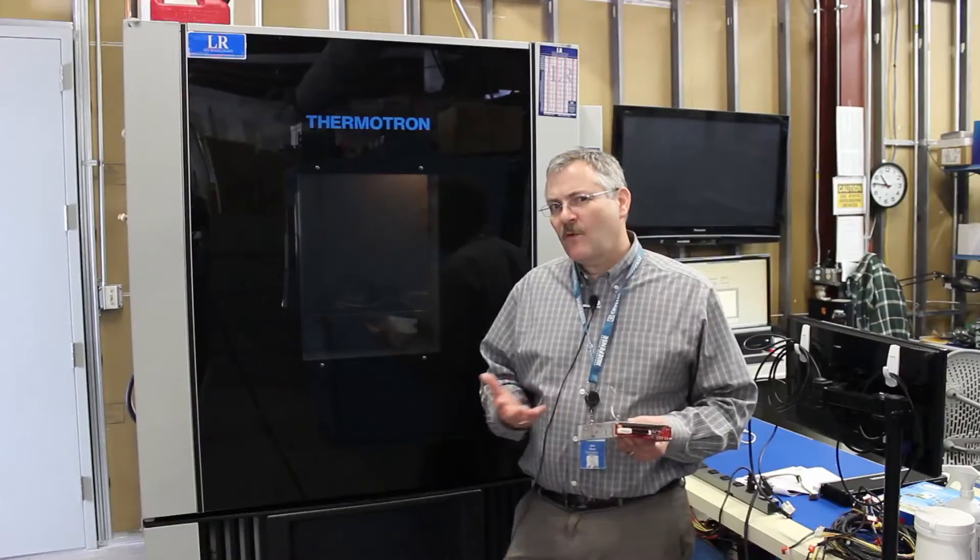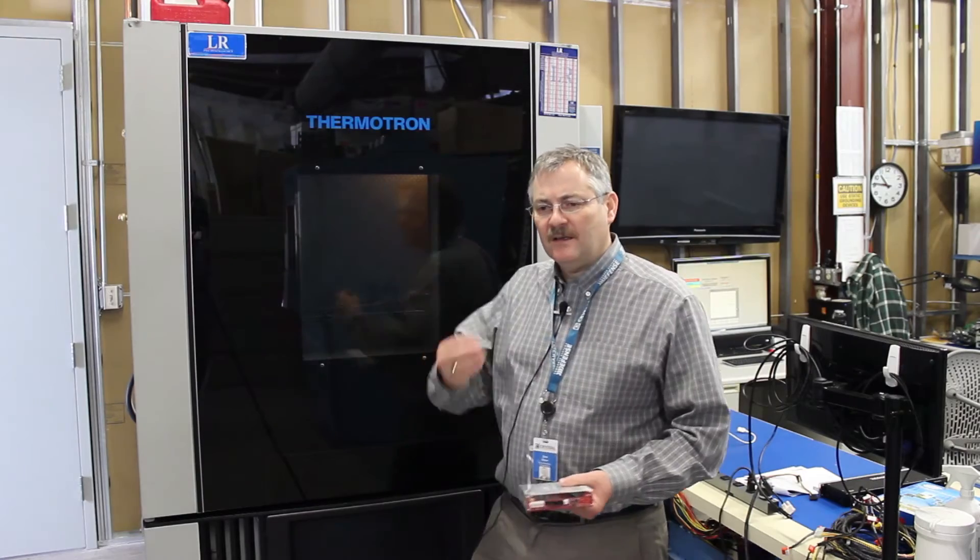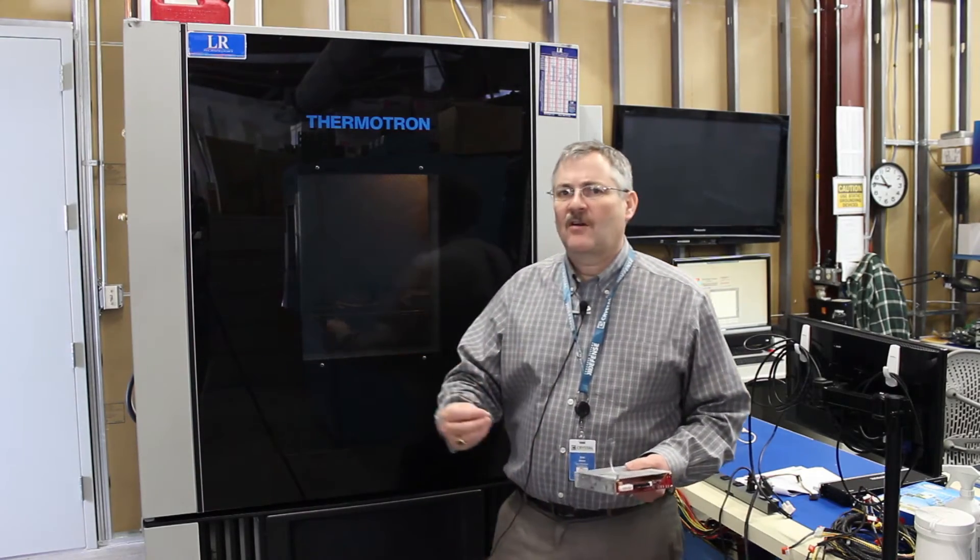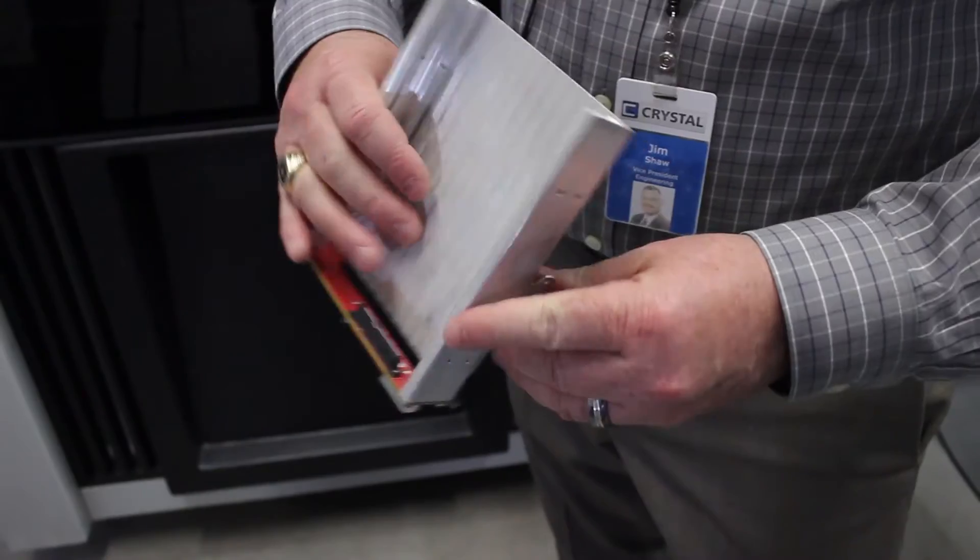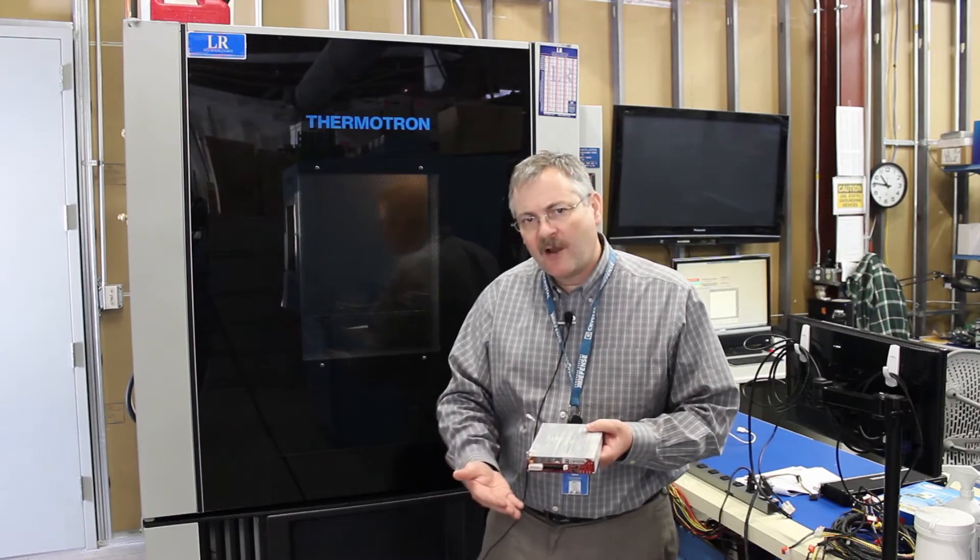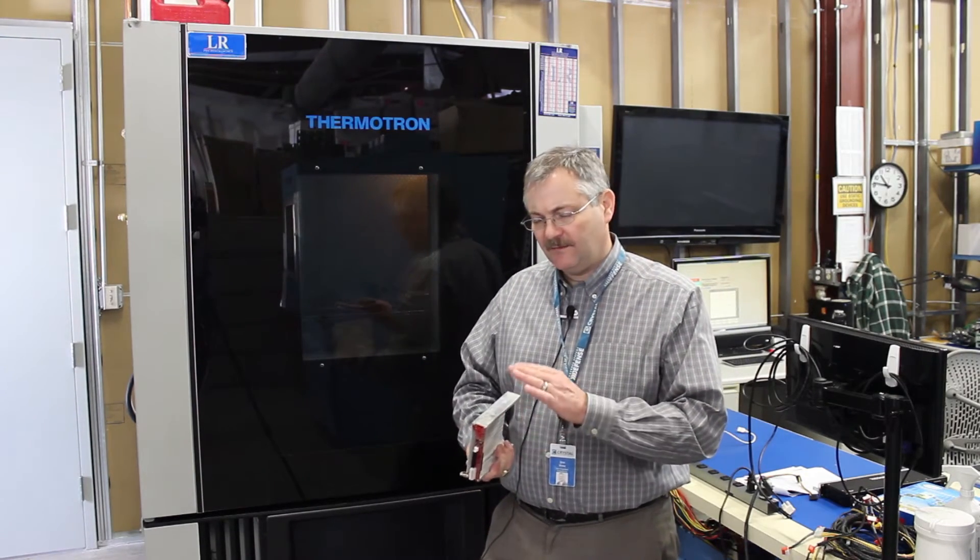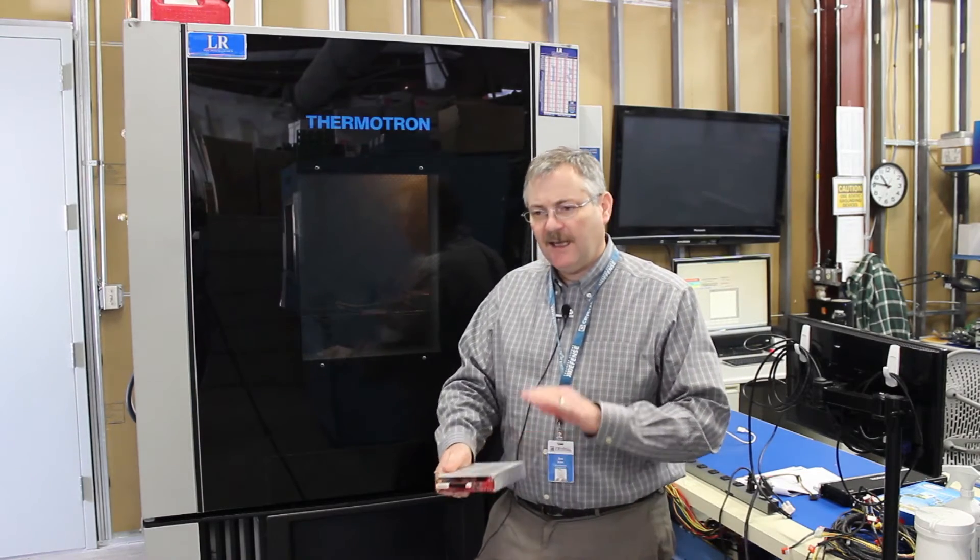So what are you looking for when you're doing these kinds of tests? This is a test about whether the moisture affects your circuit cards. Do the bonding surfaces that you're using for EMI and grounding get impacted by the humidity in the air, and does that degrade the performance of the product?